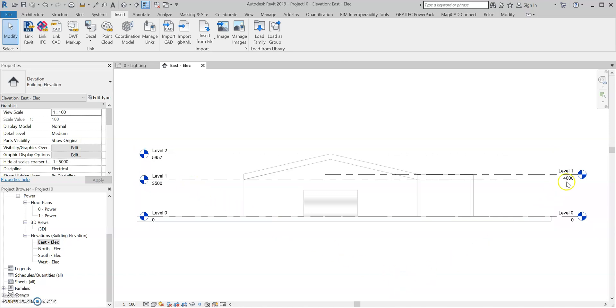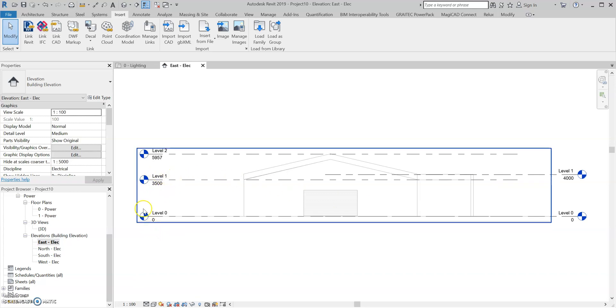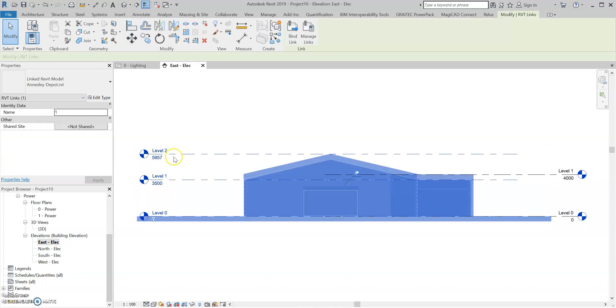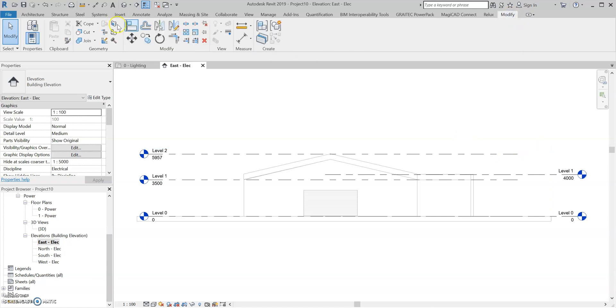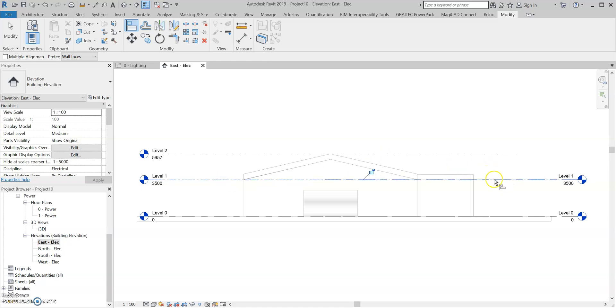We can now start adjusting our levels to match the architect's levels. I'm going to bring mine down from 4000 down to 3500, because this is the architect's level. You can't individually select the architect level, but you can with the electrical level. So I'm going to go to Modify and Align, select the architect level first, and then the electrical level second. You'll notice that went from 4000 to 3500 — you want these two numbers to match.